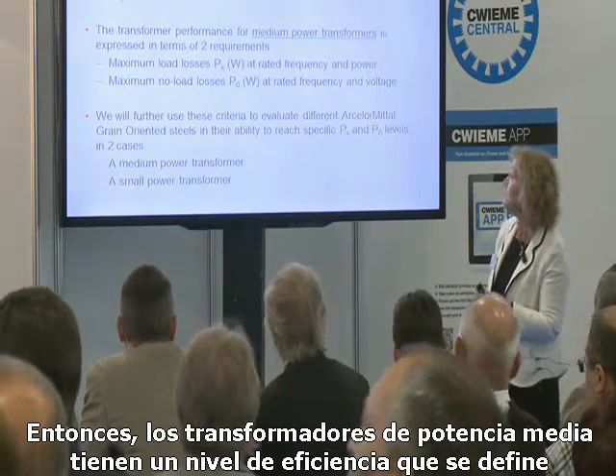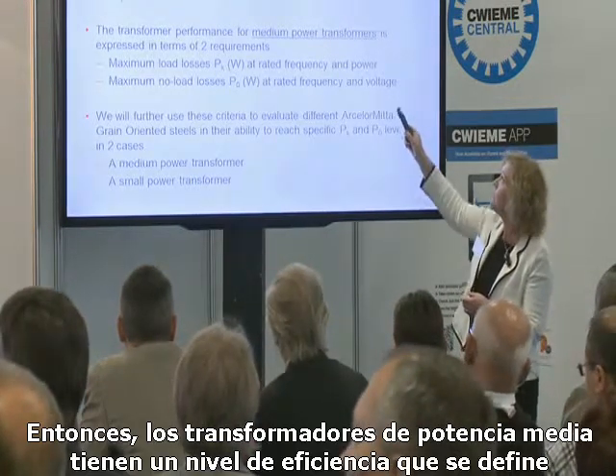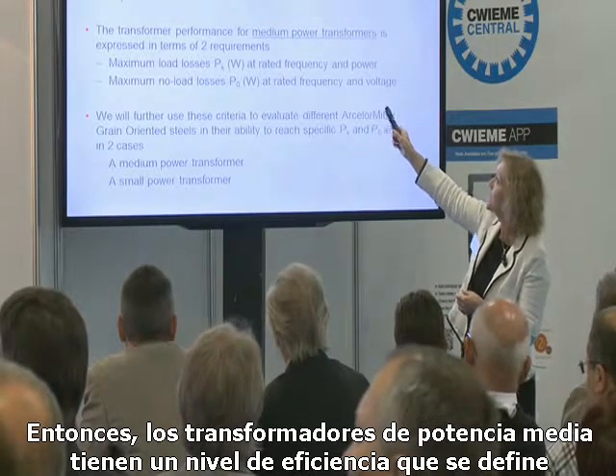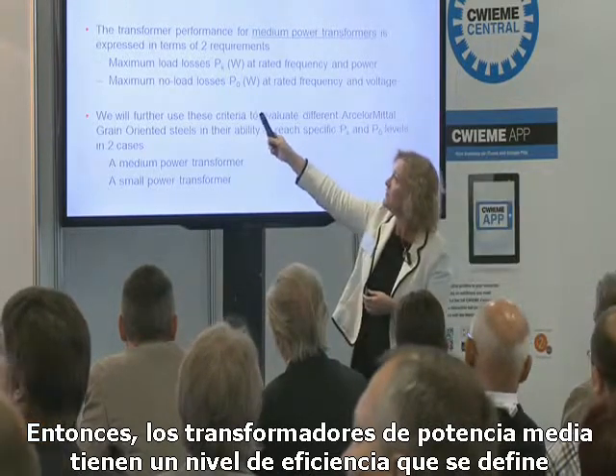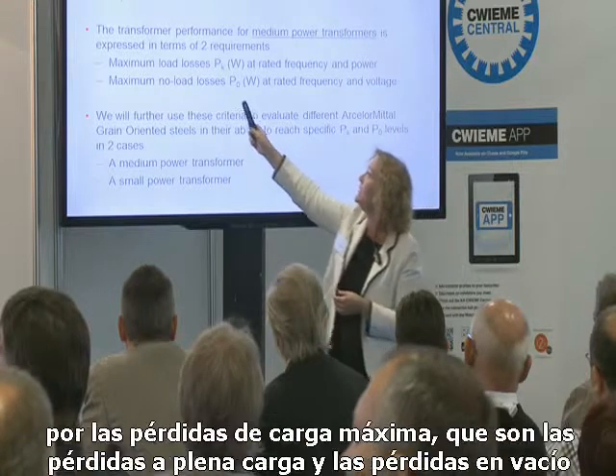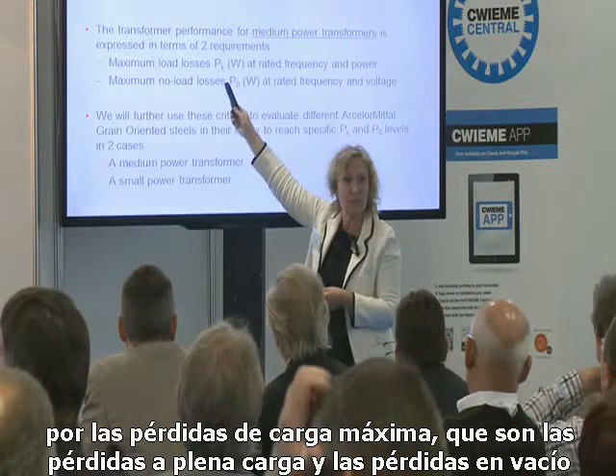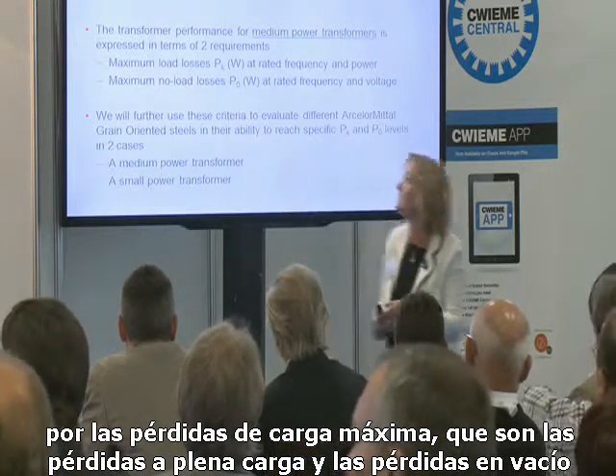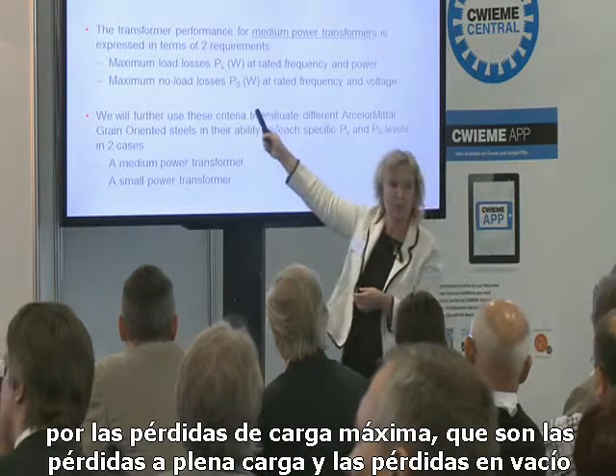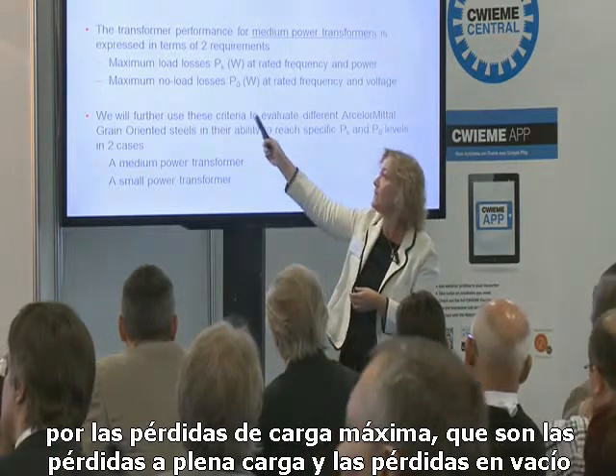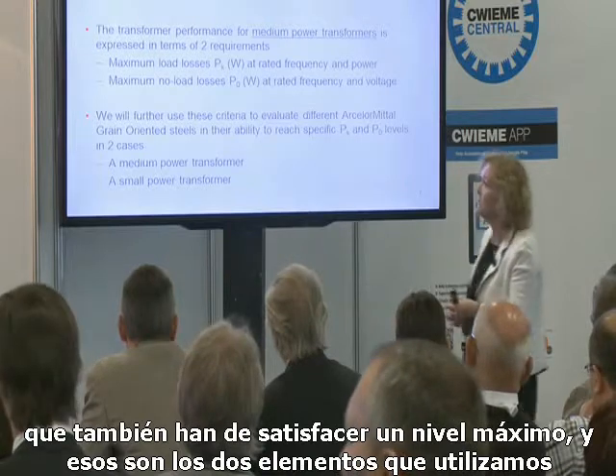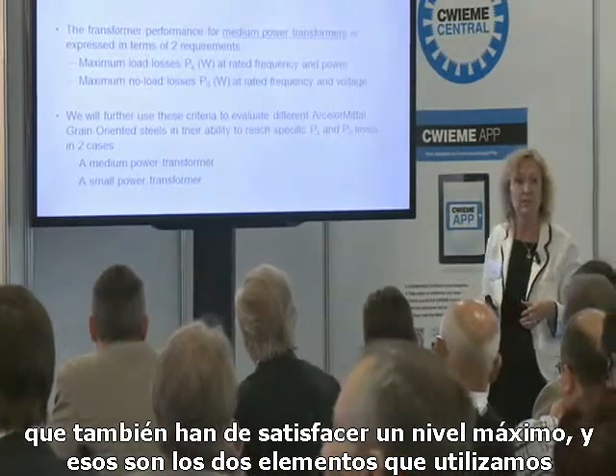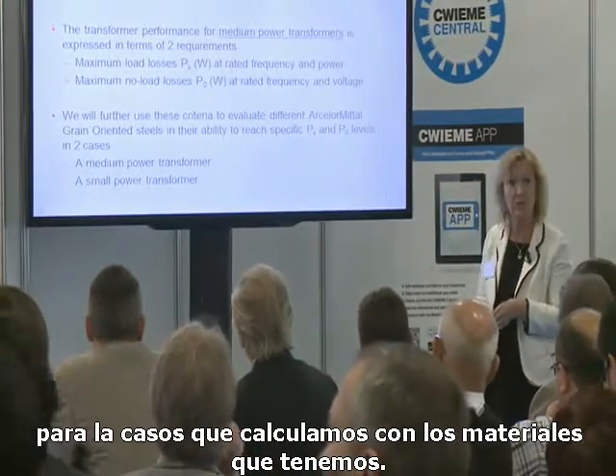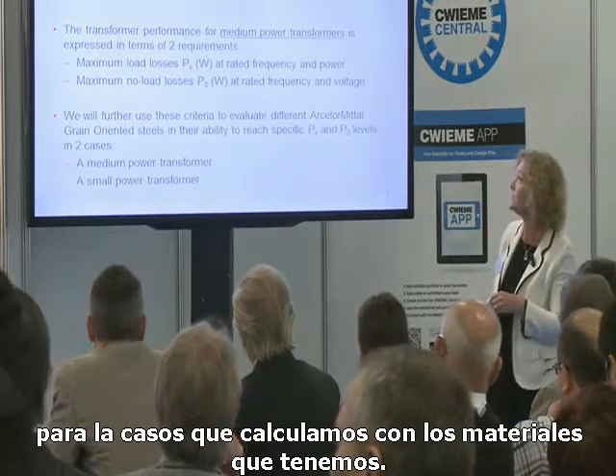Medium power transformers have an efficiency level defined by the maximum load losses, that is the losses at full load, PK, and the losses at no load, which also have to satisfy a maximum level. Those are the two elements we used for the cases we calculated with the materials we have.